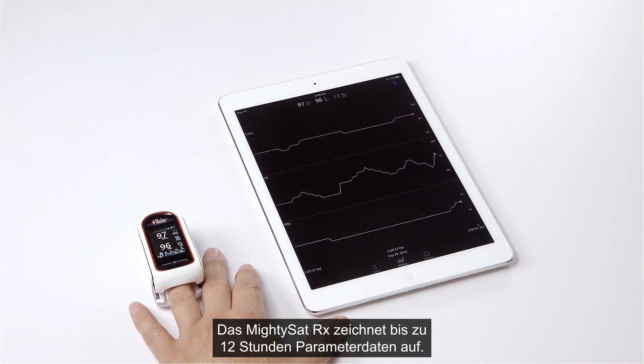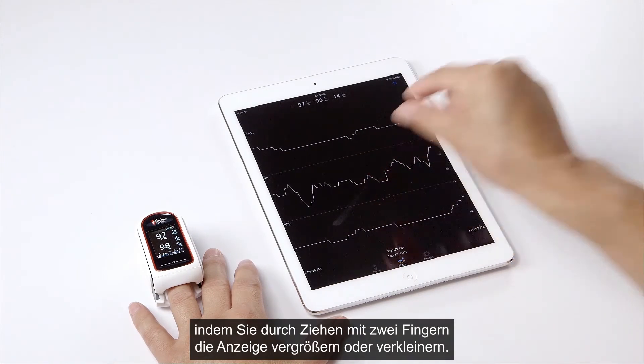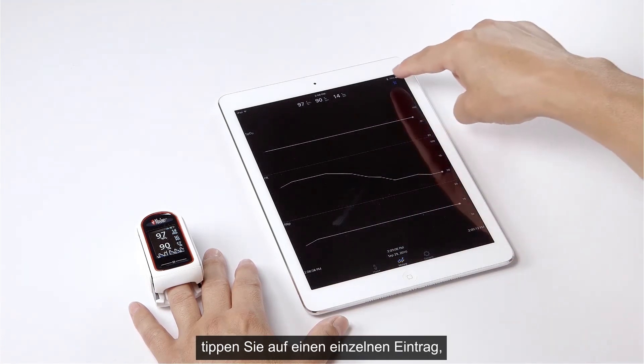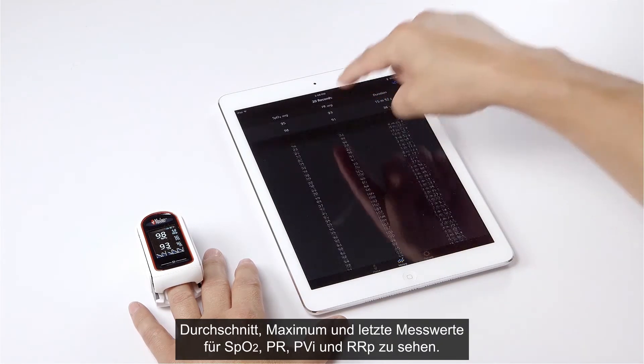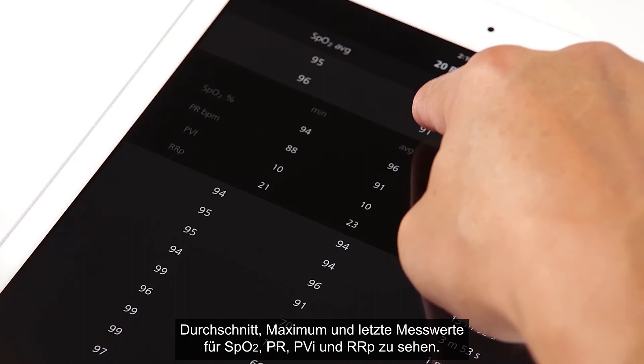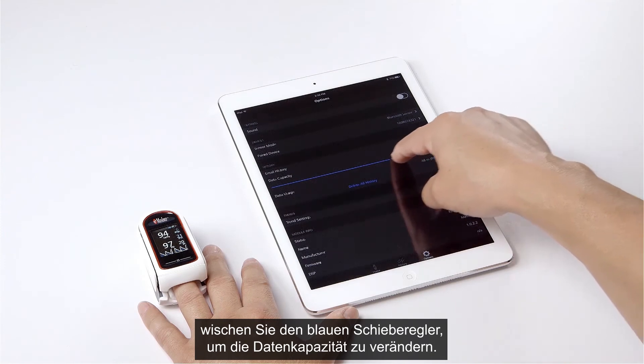The MightySat Rx will record up to 12 hours of parameter data. Toggle on the trend lines and use two fingers to shrink or expand the timescale you wish to view. To see measured parameter values, tap the blue trend icon. Tap any individual record to see detailed information including minimum, average, maximum, and last readings for SpO2, PR, PVI, and RRP. Tap the options icon and select email history to send the selected record's data via email. Swipe the blue slider to increase or decrease the timescale for recorded measurements.